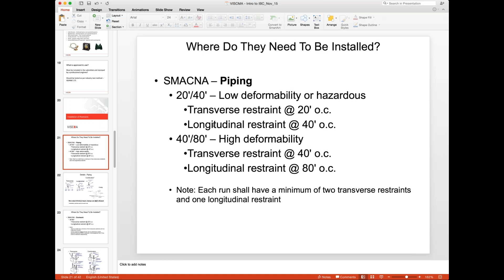The note at the bottom is very important, because if you have a run shorter than the spacing of 20-40 or 40-80, you are still required to put two transverse restraints. This prevents global rotation of the piping run by putting a transverse at each end. One longitudinal is still functional in this case, because you can slide a force along its line of action without creating a moment. So that's to prevent global rotation of that piping run — you put one at each end.